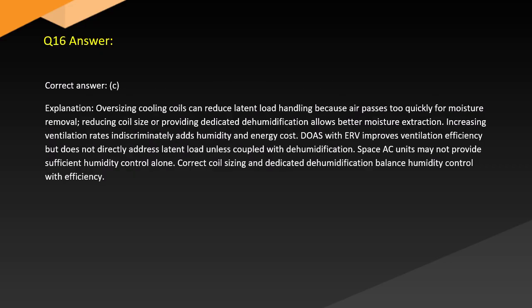Answer. Correct answer: C. Explanation. Oversizing cooling coils can reduce latent load handling because air passes too quickly for moisture removal. Reducing coil size or providing dedicated dehumidification allows better moisture extraction. Increasing ventilation rates indiscriminately adds humidity and energy cost. DOAS with ERV improves ventilation efficiency but does not directly address latent load unless coupled with dehumidification. AC units may not provide sufficient humidity control alone. Correct coil sizing and dedicated dehumidification balance humidity control with efficiency.